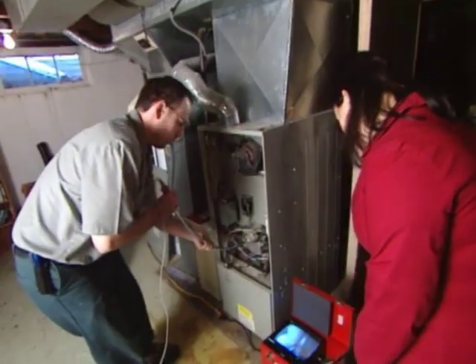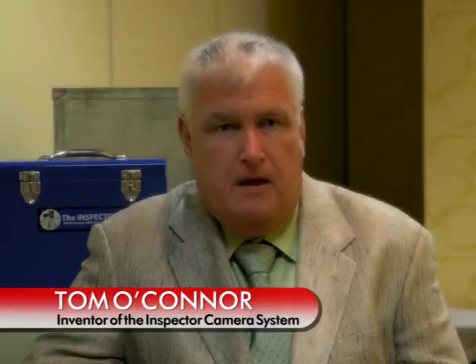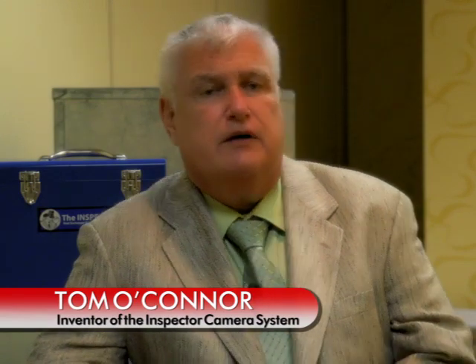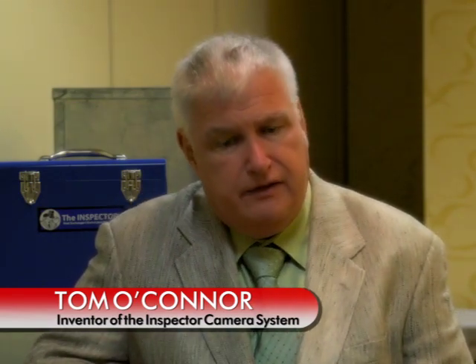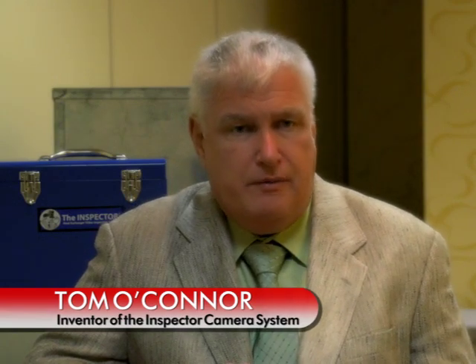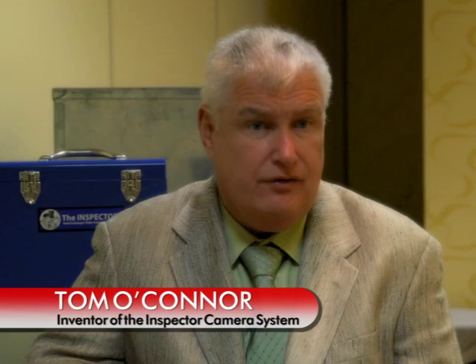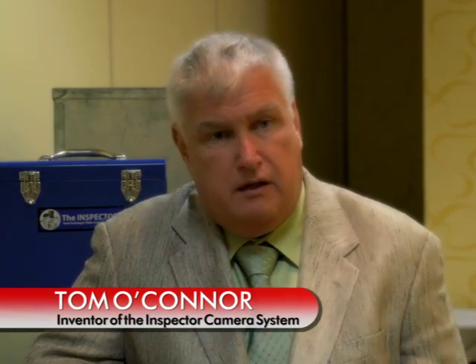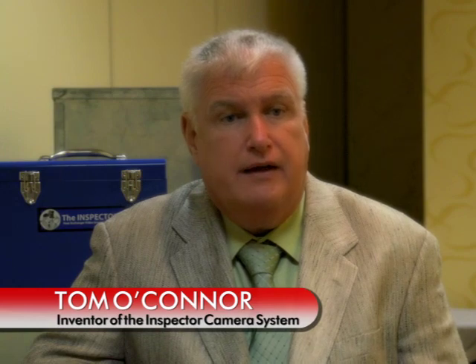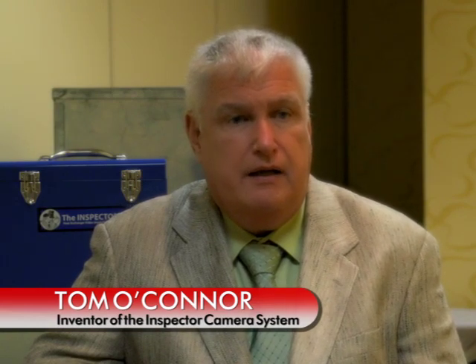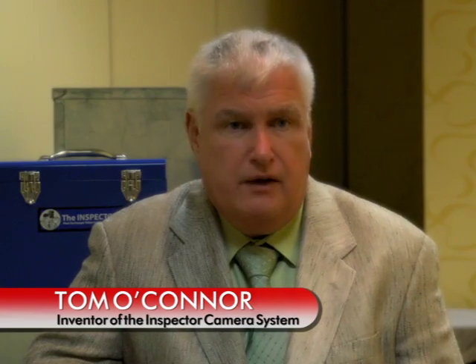The Inspector Camera allows us to better check the inner structure of your furnace than we could ever do before with older technology. It's critical to know if there's any holes or cracks in the heat exchanger, because it's what separates the combustion gases and carbon monoxide from the household air. It must be sound and intact, with no holes or cracks. In the past, we inspected it the best we could with either a candle or a flashlight with a mirror.